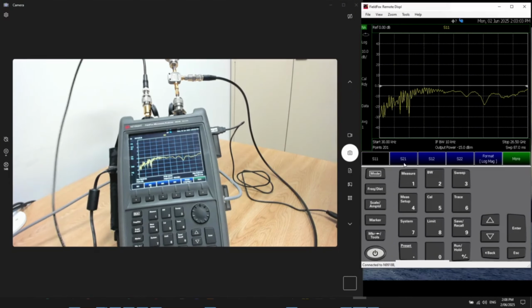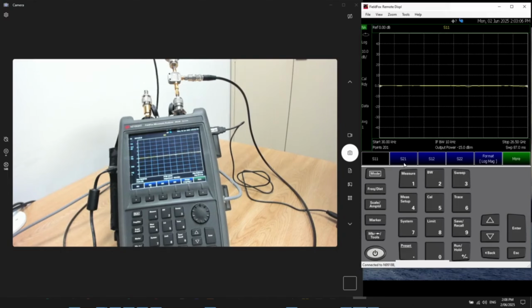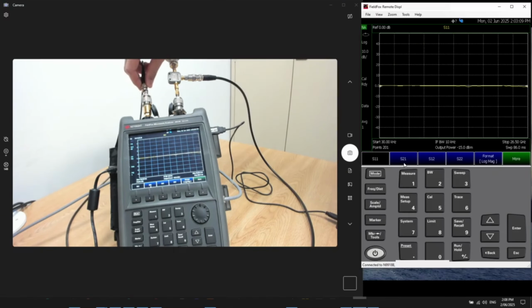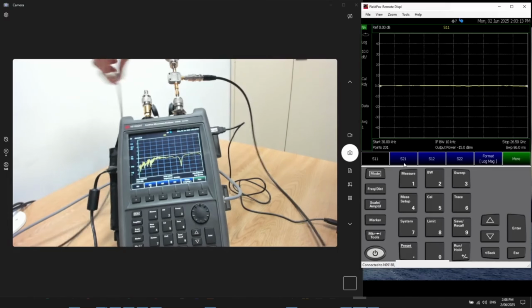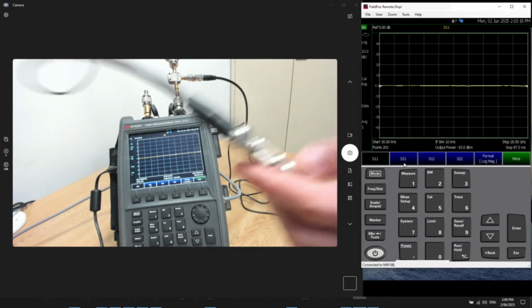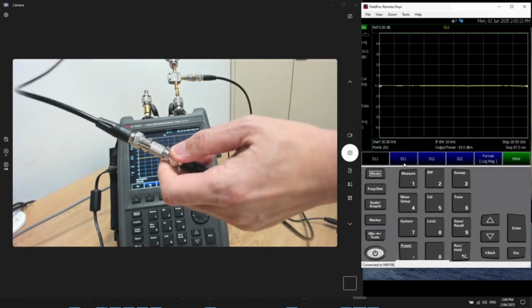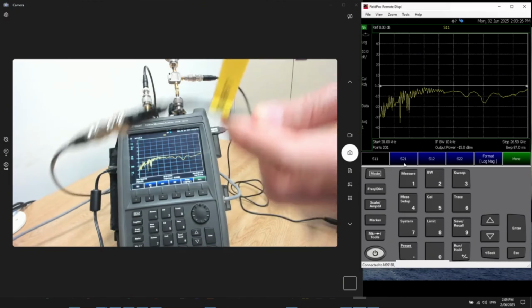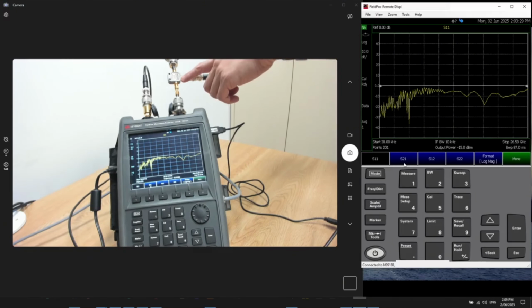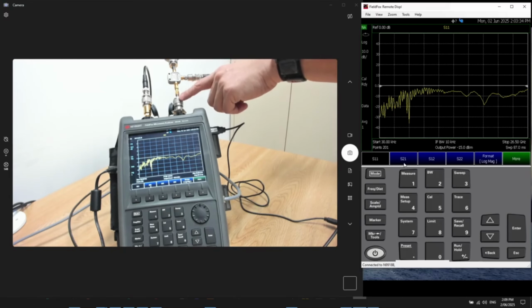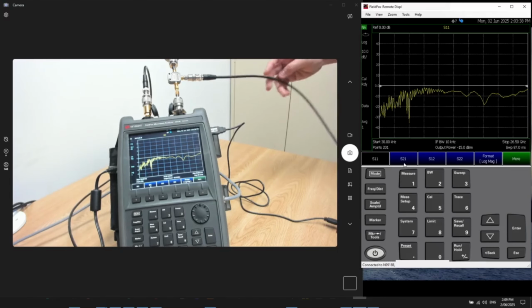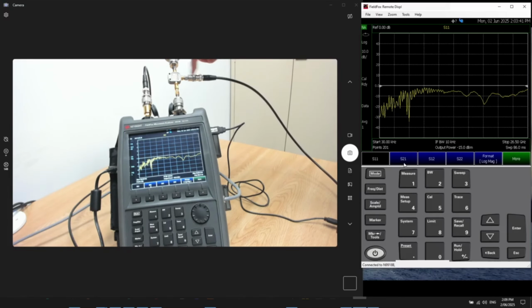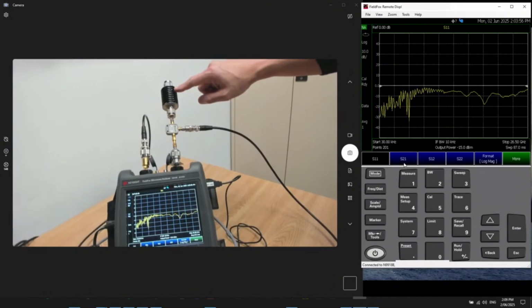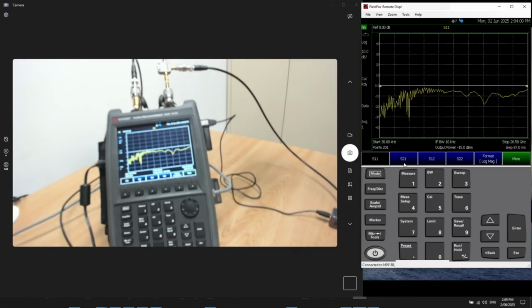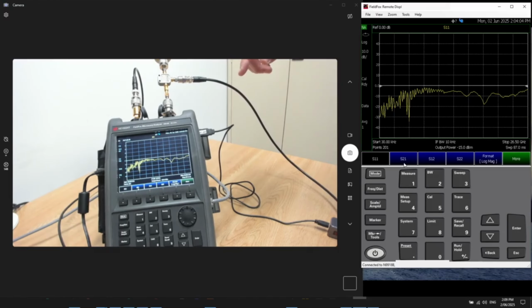As you can see here, I have port 1 connecting to a BNC cable. It's just a normal BNC cable plugged in here. And I try to make it the worst case scenario with the connections. So I have one cable, and you can see that there's a barrel connecting to another BNC cable. And then from the other end, I'm connecting it to the input port of the power splitter. And one splitter output is connecting back to port 2 of the FieldFox. So essentially what we want is from port 1 entering here, and then we do an S21 measurement between the common port and the side port. The other end is connected to an attenuator just to remove the reflection effect. But this is how it looks right now.